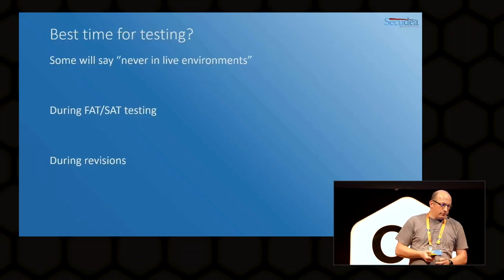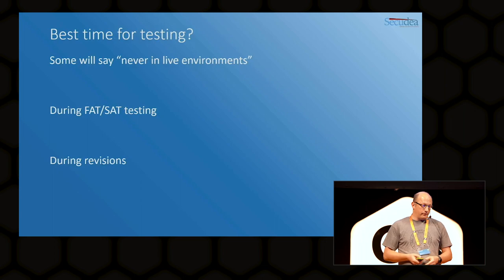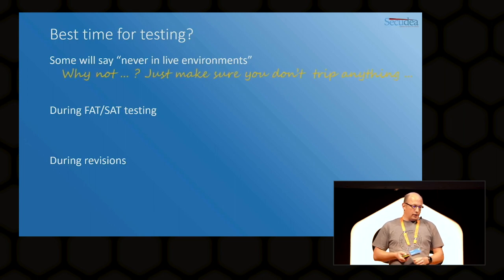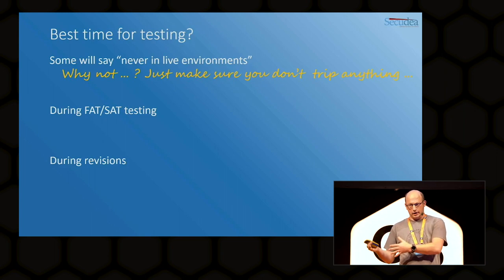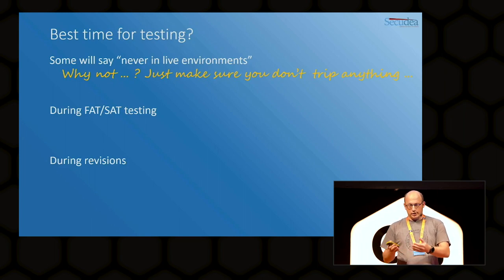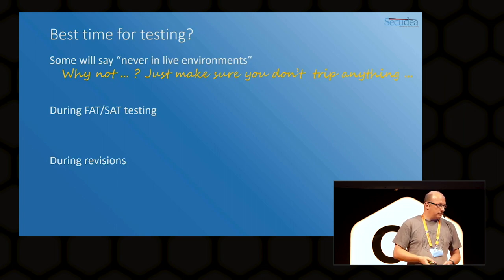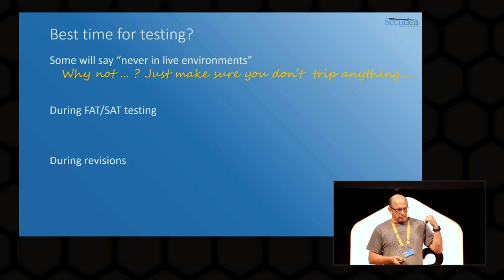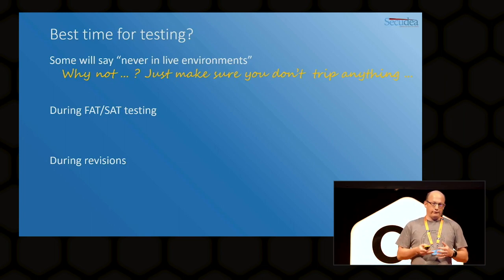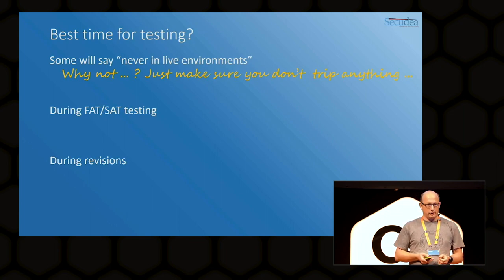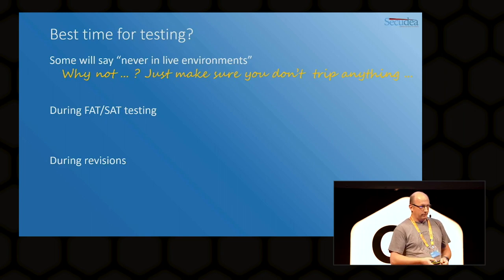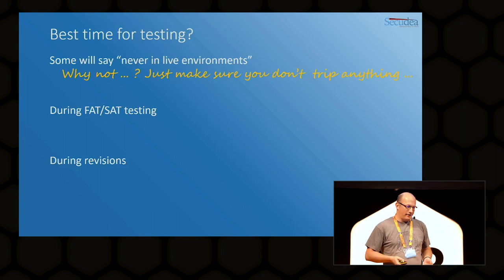Now, what is the best time for testing? Some say never in live environments — that's already been said today. Some say during FAT/SAT testing, always during FAT or during revisions. Never in live environments — I tend to say, why not? If you know what you're doing, if you have your customer with you, just make sure you know your limits. Don't scan the PLCs running the system, but Windows systems — why not? One customer gave me a mandate to scan until I could affect production — that was a 3-gigawatt power facility. I've never reached the point of impacting production, yet.